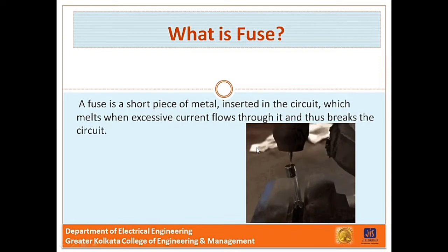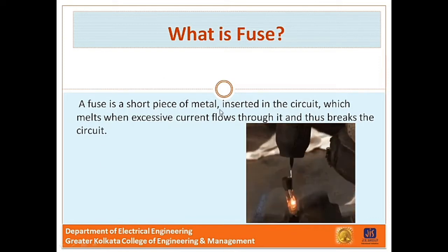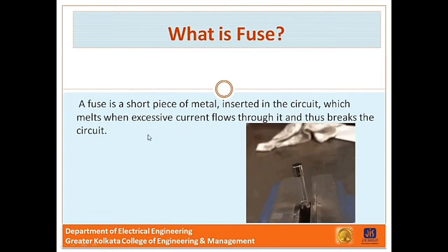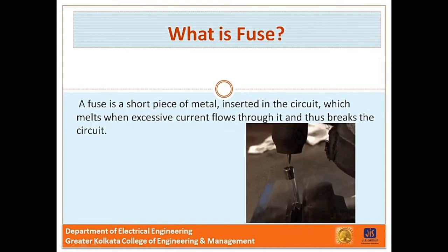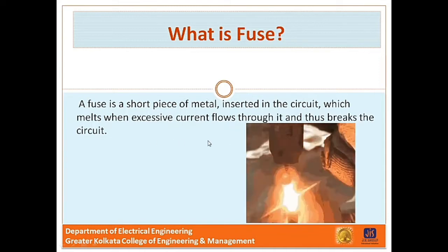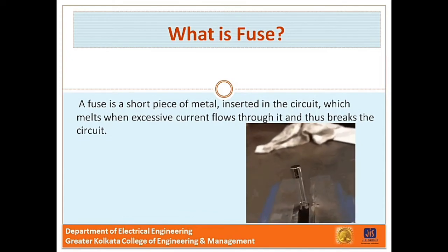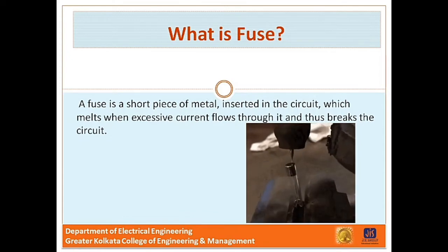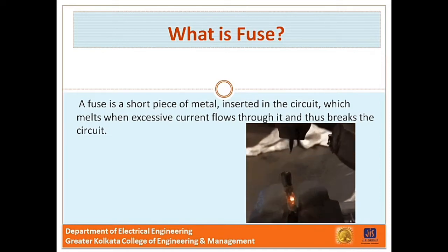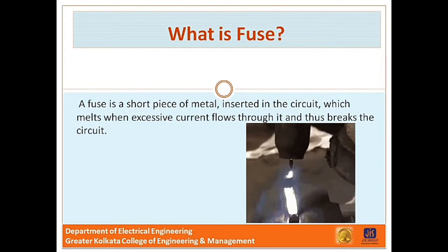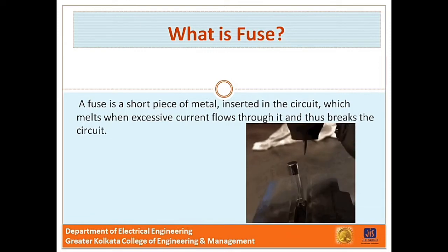What is a fuse? A fuse is a short piece of metal inserted in the circuit which melts when excessive currents flow through it and thus breaks the circuit. The fuse element is generally made of material having low melting point, high conductivity, and least deterioration due to oxidation. It is inserted in series with the circuit to be protected.